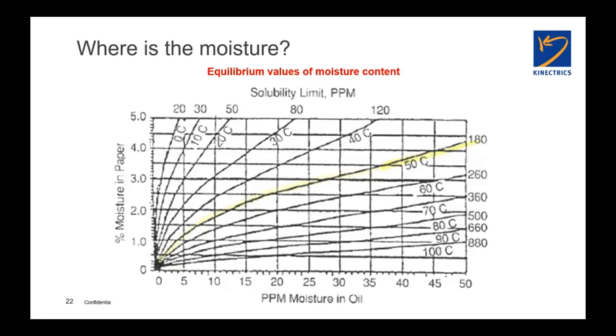Periodic oil sampling is just that. It's typically once a year. Stuff can happen the day after you take the oil sample. Online is 24/7, 365. I can tell you though, and I'm not speaking so much about moisture, I've done a number of forensic studies where a transformer failed, and the monitor on the transformer clearly showed two or three hours before the failure occurred that there was going to be a problem, but that was at 2 a.m. and there was nobody there to listen, so to speak. If a tree falls in the forest and there's nobody there to hear it, same kind of thing.